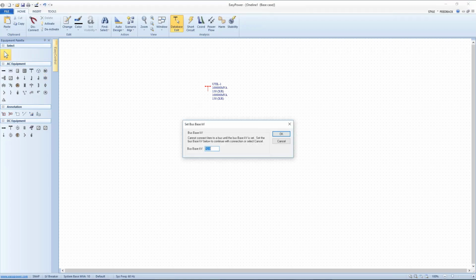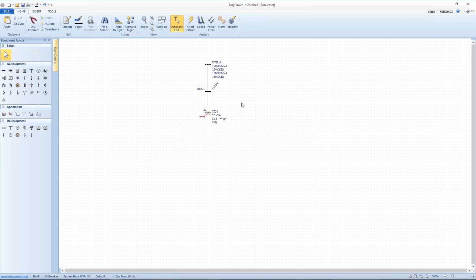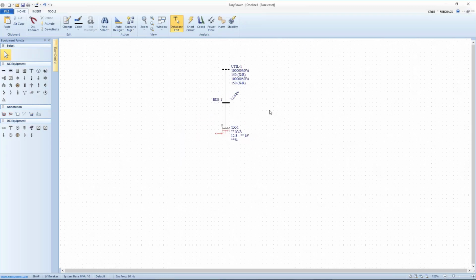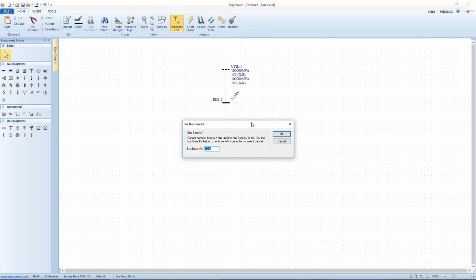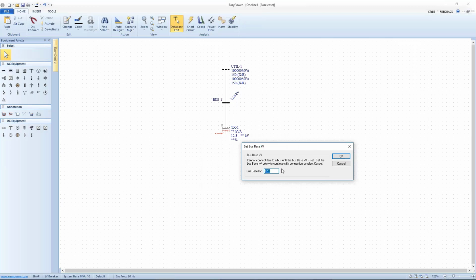He says, "Well, here." So we were on a call very much like this, and as he described his system, he had me build a one-line diagram. So we take the utility icon and we connect the two-winding transformer, which in this case was the utility transformer. And he said, put a bus on the secondary side of the transformer. Now you notice as I do this, the tool recognizes that there's a need for an assignment of voltage. His incoming utility was at 12.8 kV. He said his distribution system was at 480 volts. So I type in 0.48.